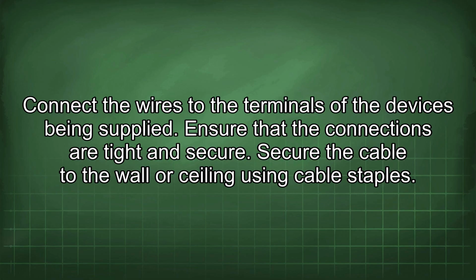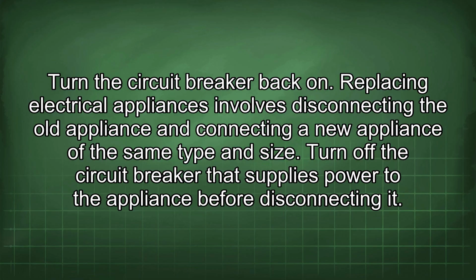Connect the wires to the terminals of the devices being supplied. Ensure that the connections are tight and secure. Secure the cable to the wall or ceiling using cable staples. Turn the circuit breaker back on.